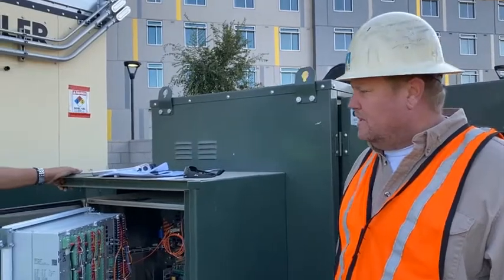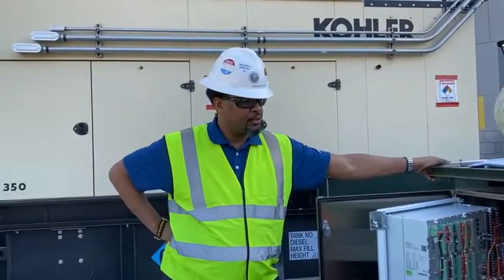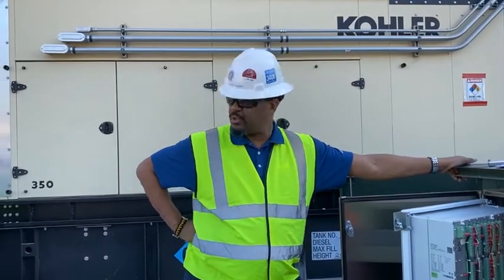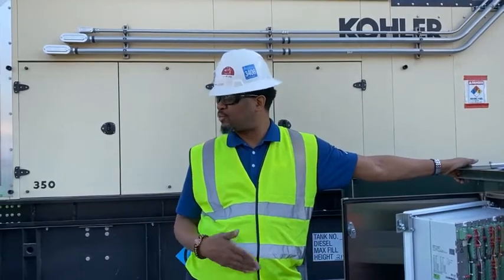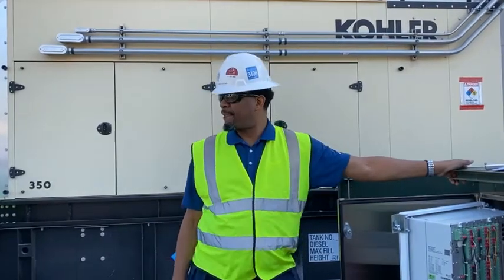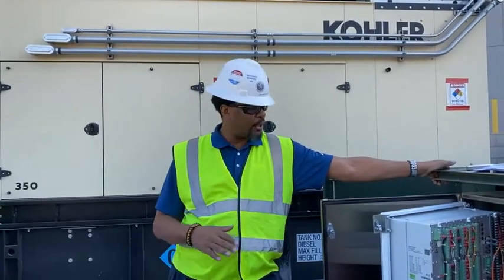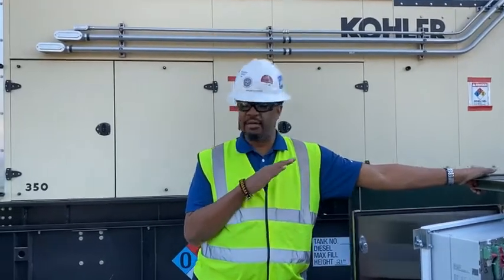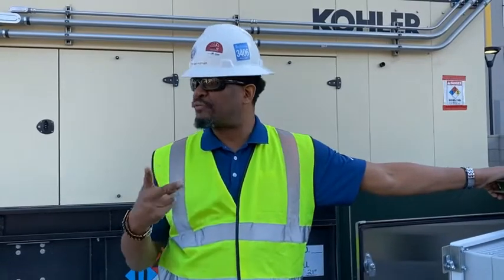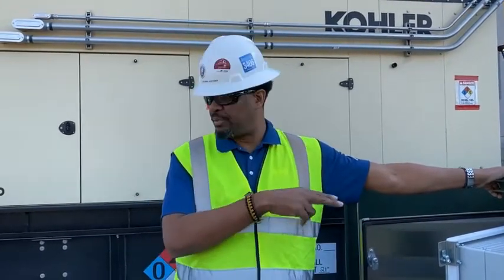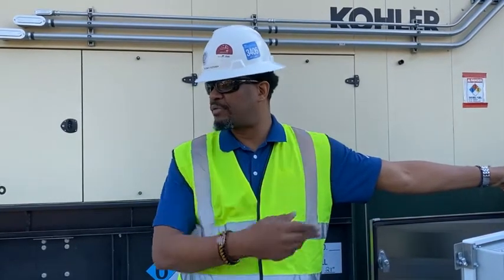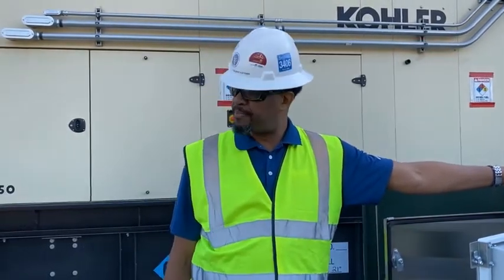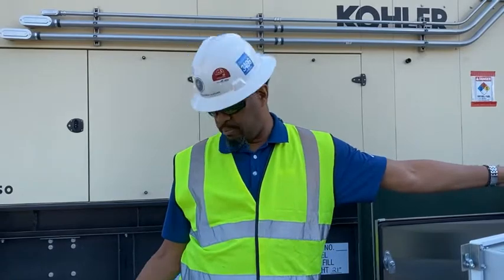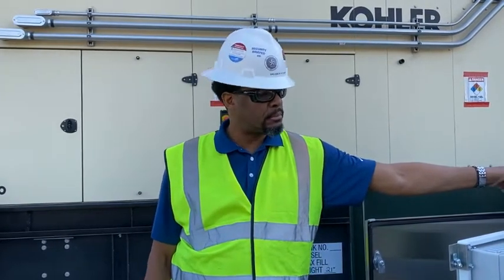Just as a point of clarification, the fans are actually 120 AC, so you don't have any draw on the batteries when it comes to that. If I lose power, the fans will shut off - right, the only way the fans would run is off 120, so you'd have to lose both sources. If it were a DC fan, then you'd be talking about draw because it'd be coming off the 24 side. But if you lose that 110, there's nothing going on in there anyway.